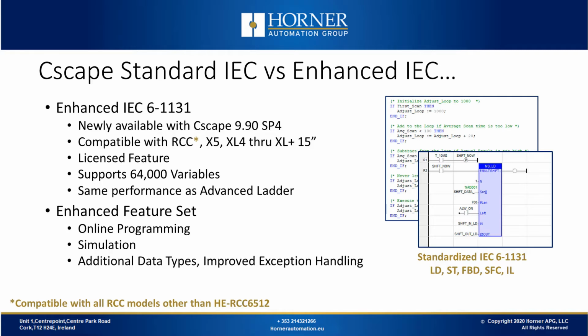Enhanced IEC is newly available with Cscape 9.90 Service Pack 4. It's compatible with the X5, the XL4 through to the XL Plus 15, and with all RCC models except for the 6512 high-speed coprocessor. It's a licensed product. You're no longer limited to 10,000 variables. We can support 64,000 variables, and there's no longer a performance hit.